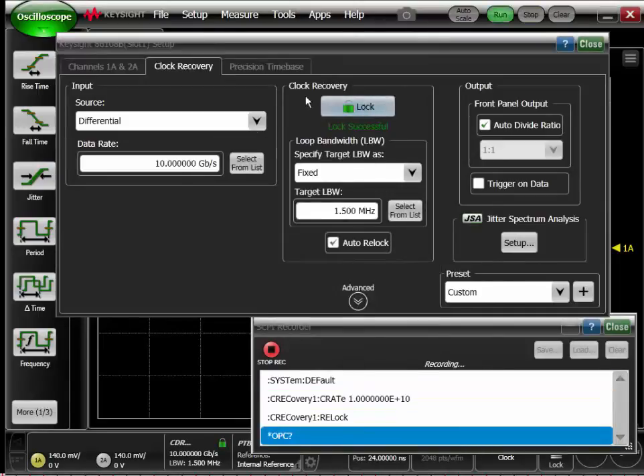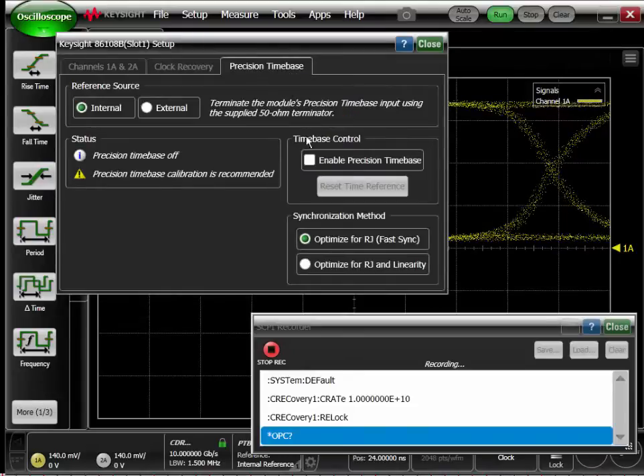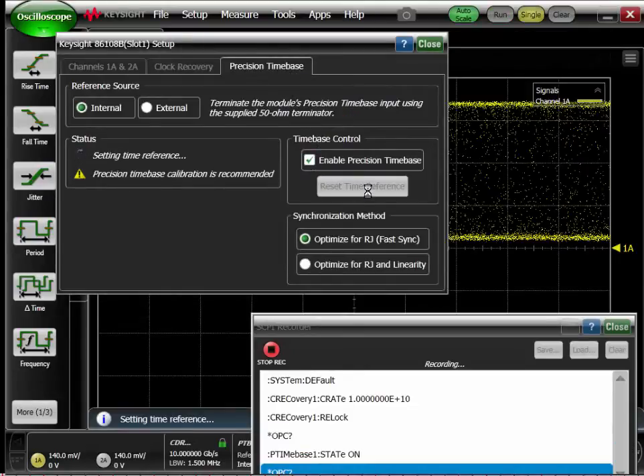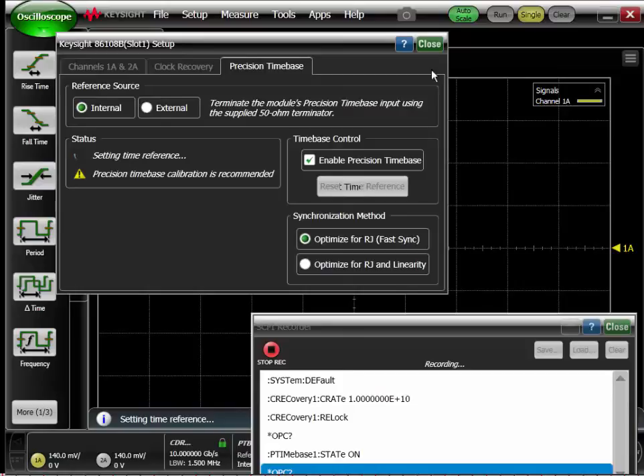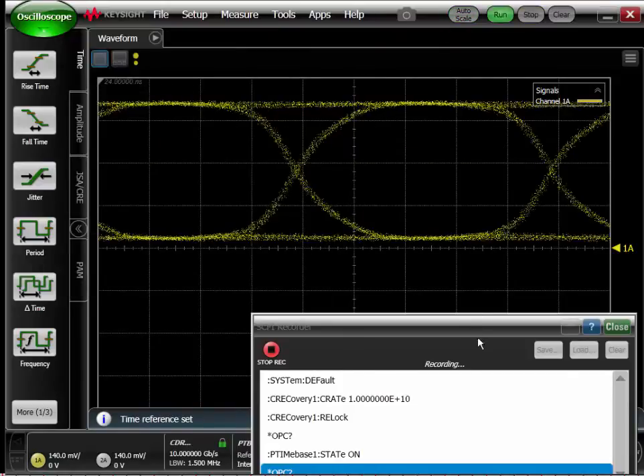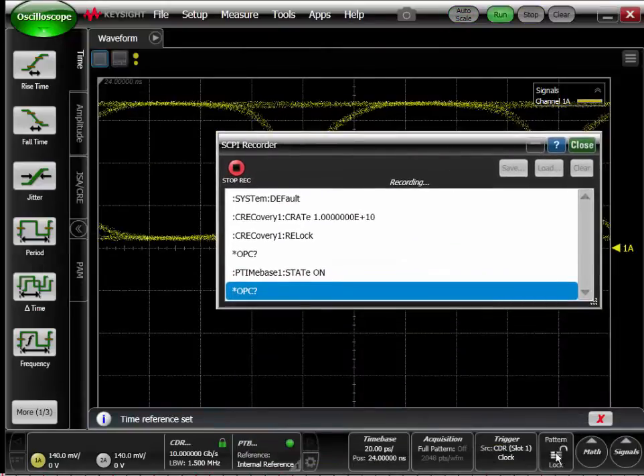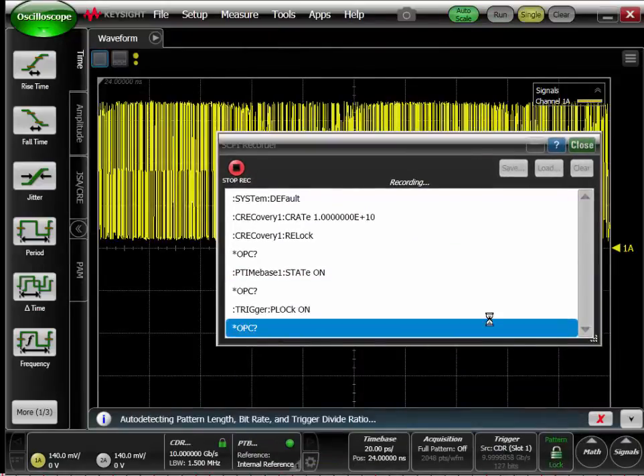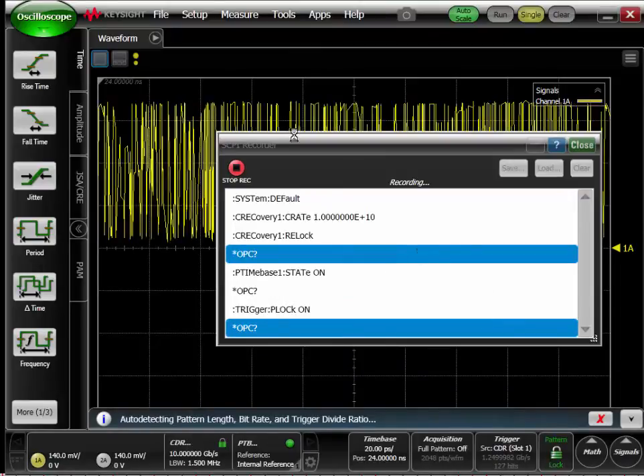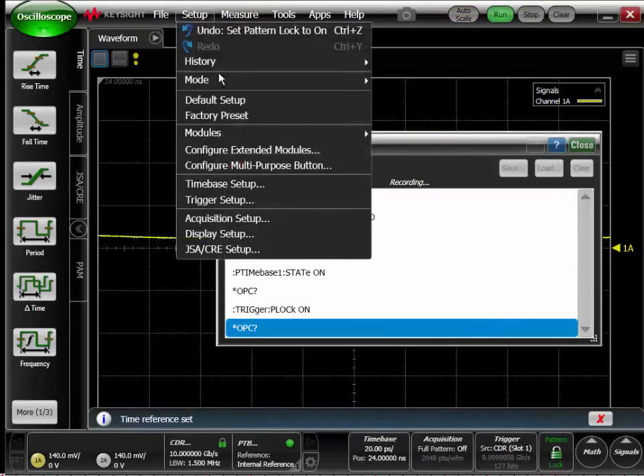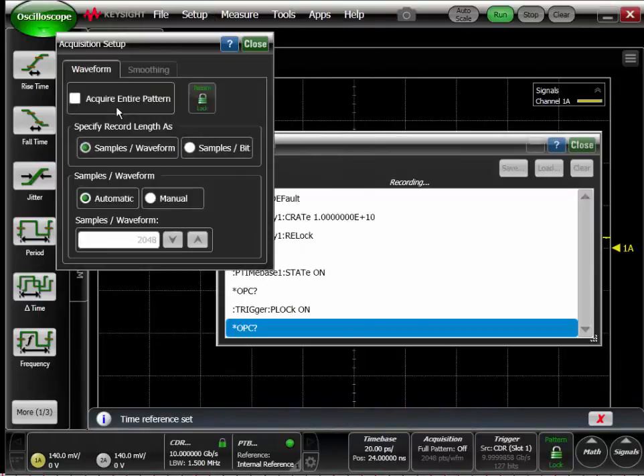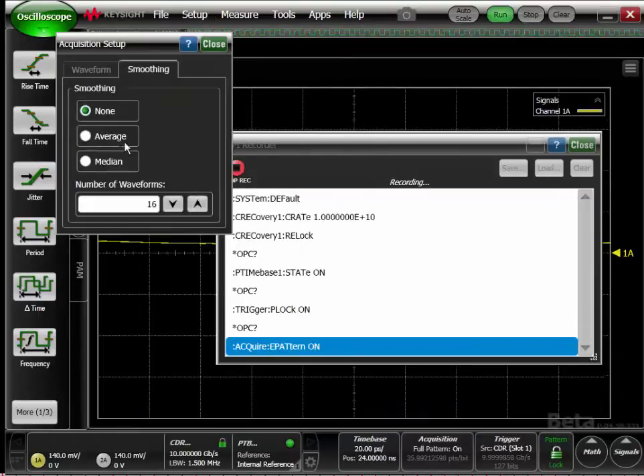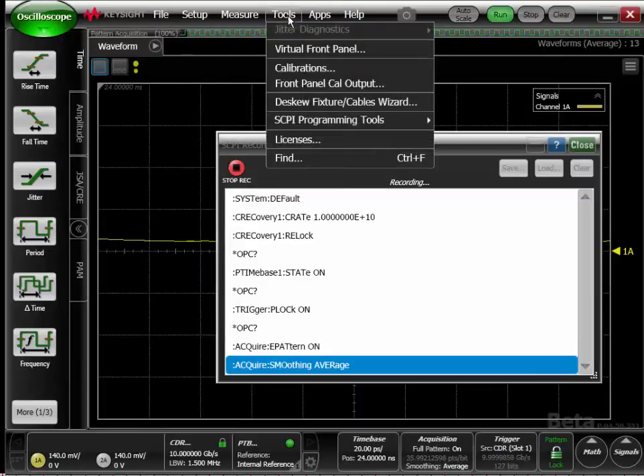In this case, I'm going to set the clock data recovery for 10 gigabit per second. I'm going to lock onto the signal that's being input to the front of the 86108B module. We'll turn on the precision time base, and I just want to pattern lock the signal. I also want to make sure we're going to acquire the entire pattern.